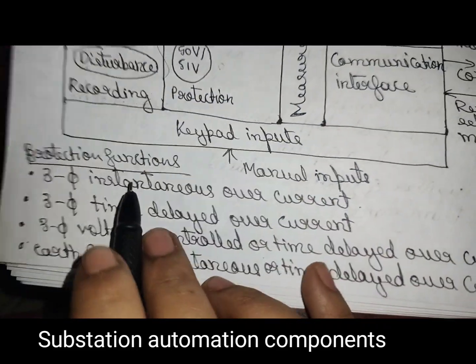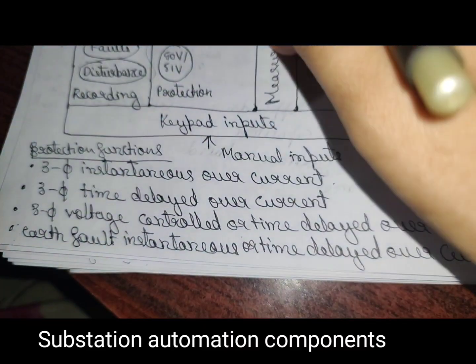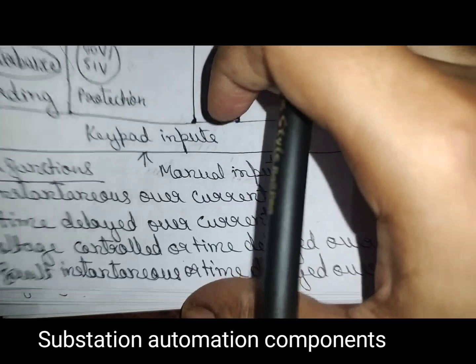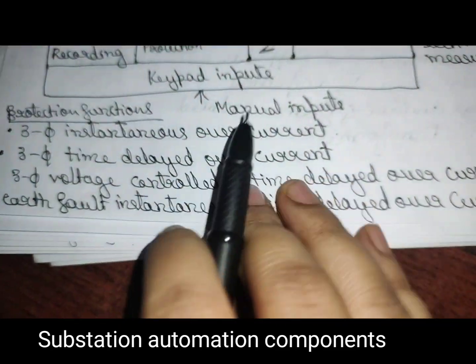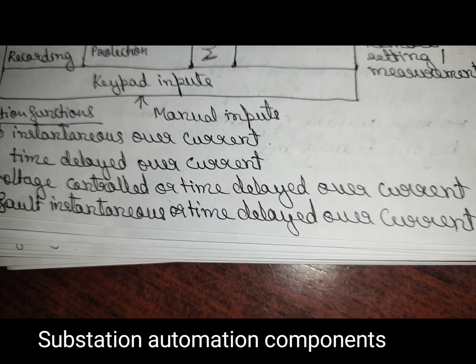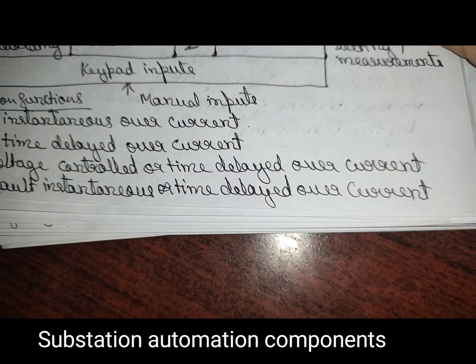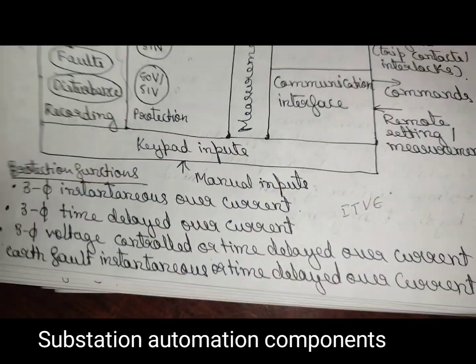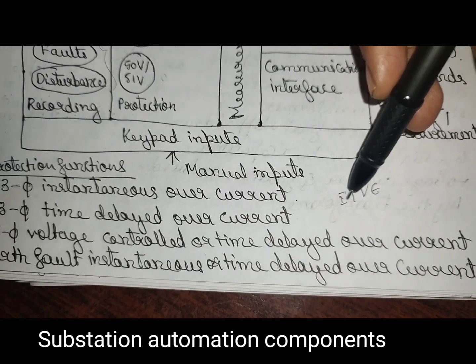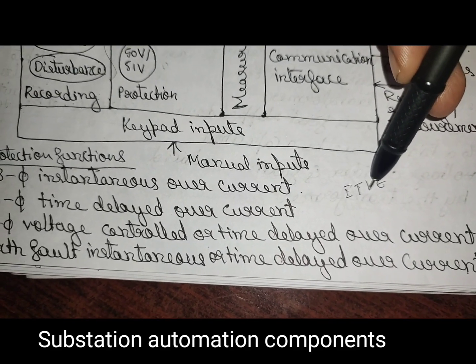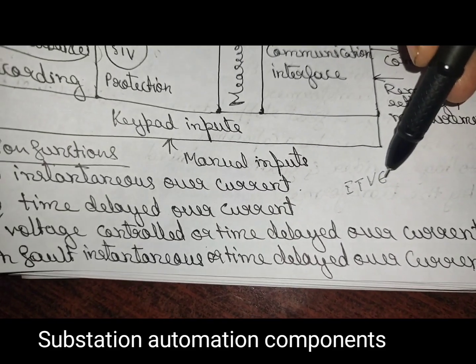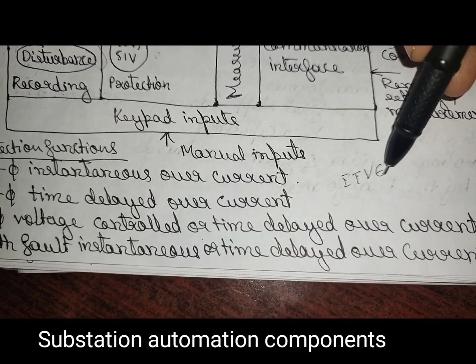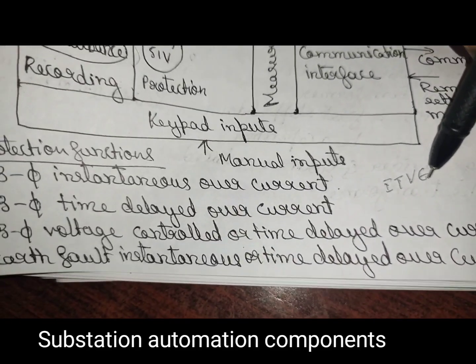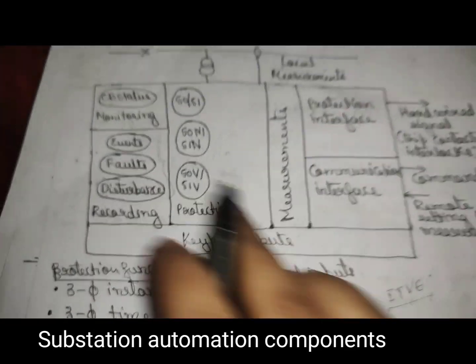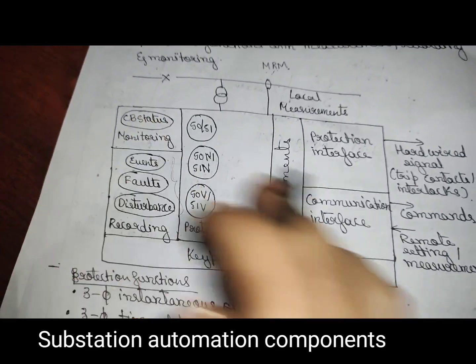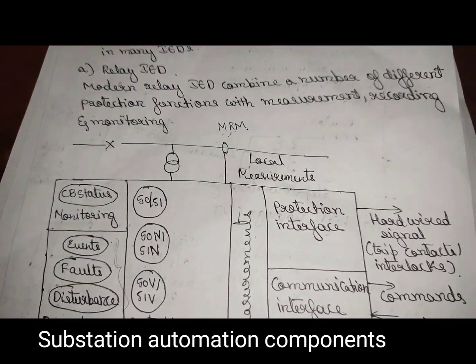So the protection functions are three-phase instantaneous overcurrent, three-phase time delayed overcurrent, three-phase voltage controlled time delayed overcurrent, and earth fault instantaneous or time delayed overcurrent. So you can remember ITVE. In the protection relay IED, ITVE. Okay, this is a relay IED.